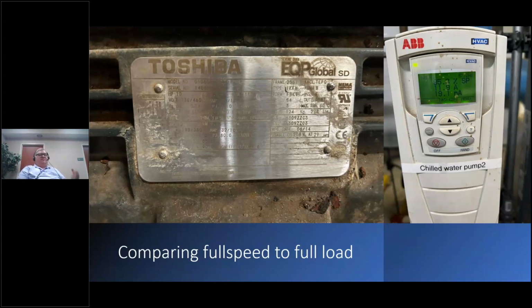Remember, those of you who were on the pump webinar, you can shut off the flow to a pump and it's still going to pull amperage, even at full speed, but it's not going to be anywhere close to full load amperage. It's not moving any water down the pipe. It's not overcoming any resistance. It only brings up amperage and horsepower when it's moving water.